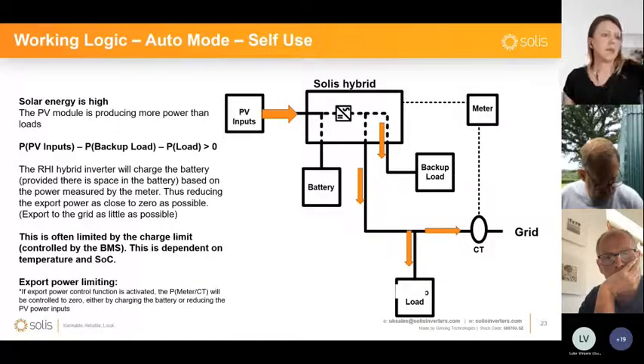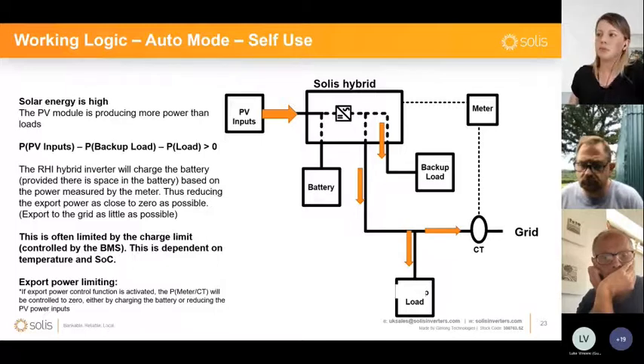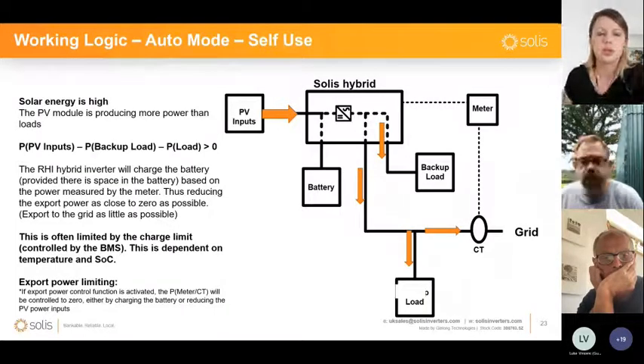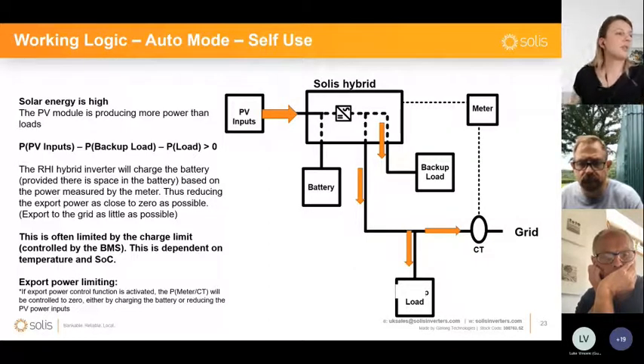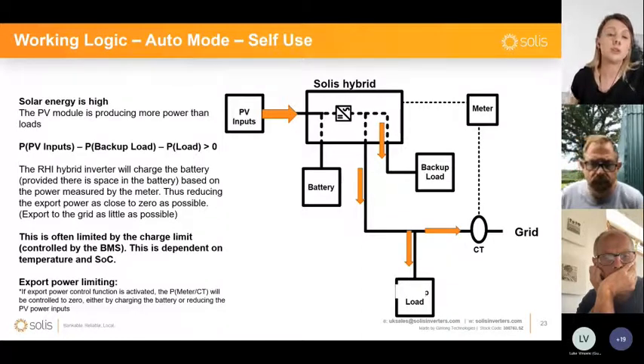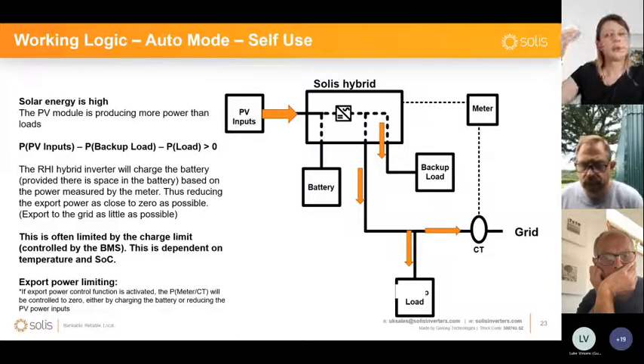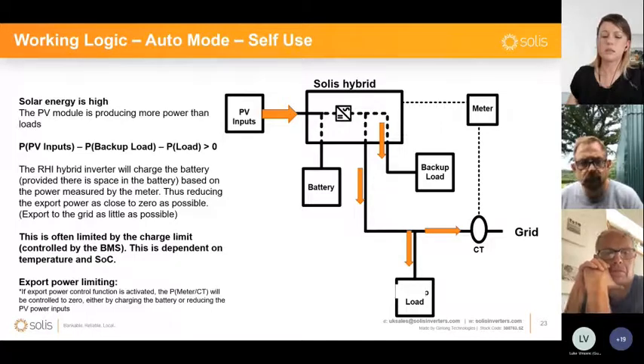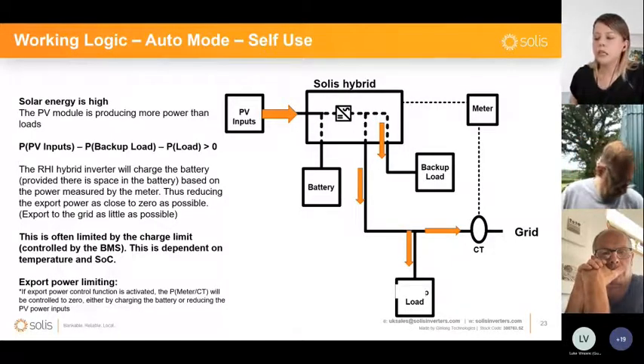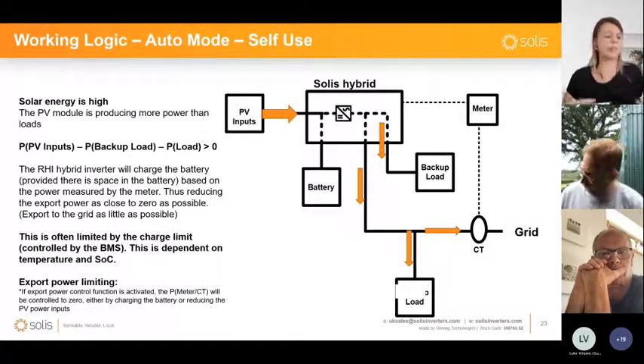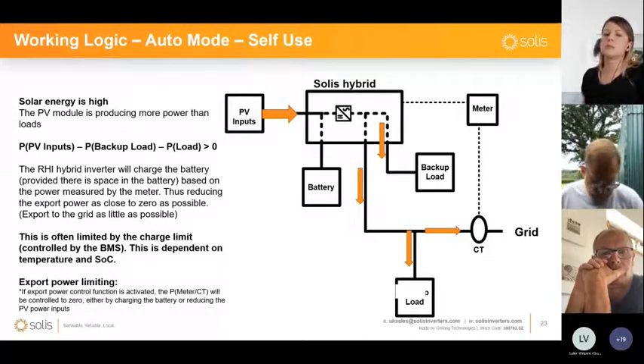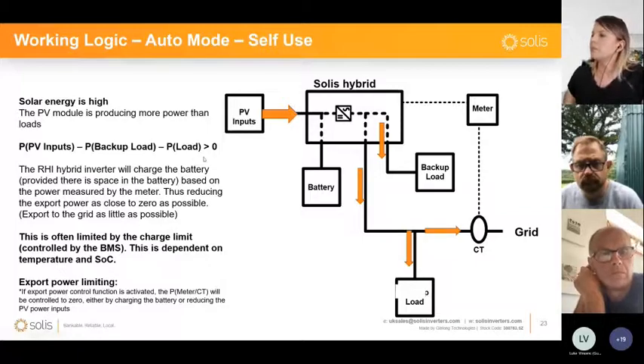For example, if a battery is completely full, the BMS will set a zero charging limit to the inverter, so it will not allow the inverter to push more energy into the battery. But this can also happen depending on the state of health of the battery, or in order to maintain good health. That limit can sometimes be lowered. For example, you can have a 50 amp limit coming in from the battery, but sometimes for lower temperatures it can even drop to 10 amps. I have seen it many times when batteries are installed during winter time in colder places. We have seen that the battery management system is limiting the current in order to maintain the health of the system.